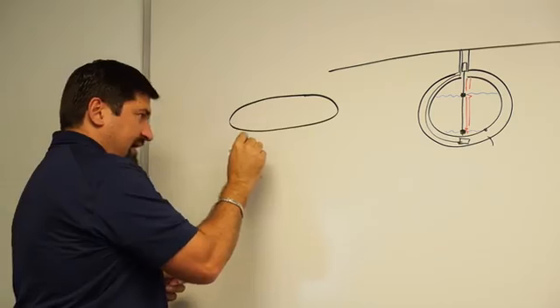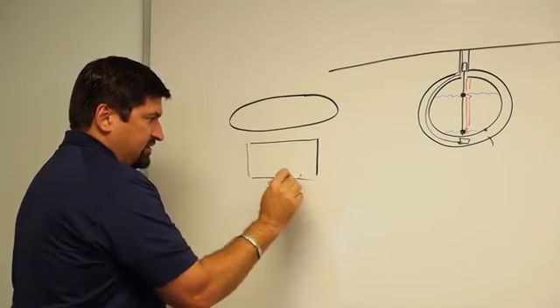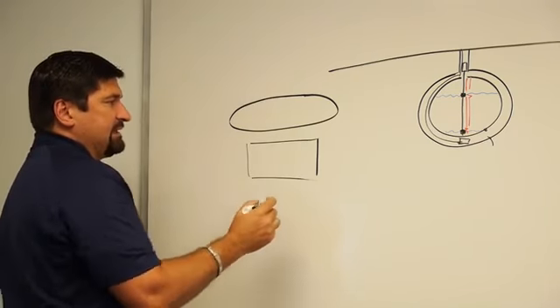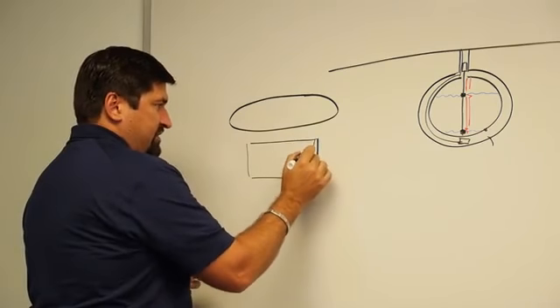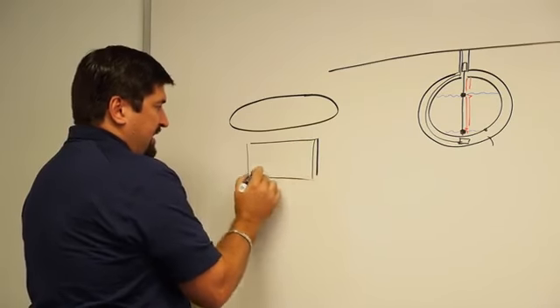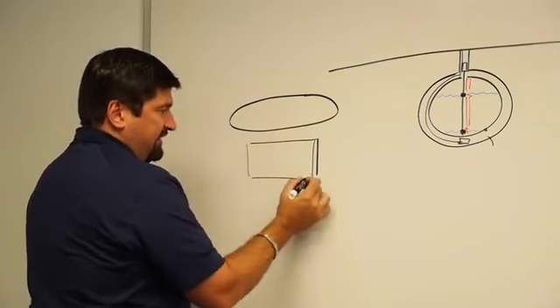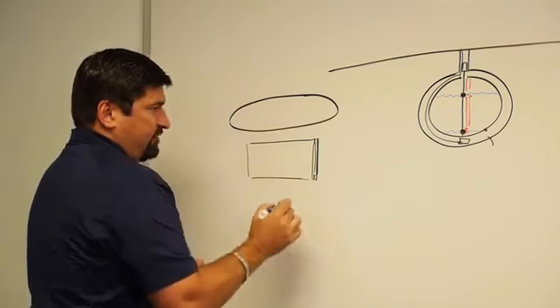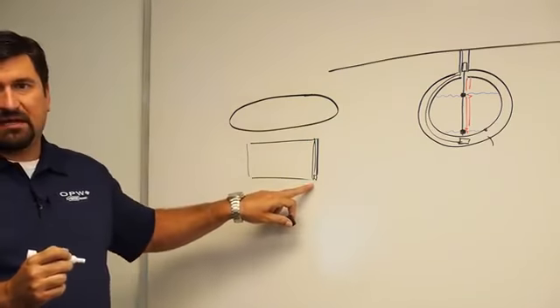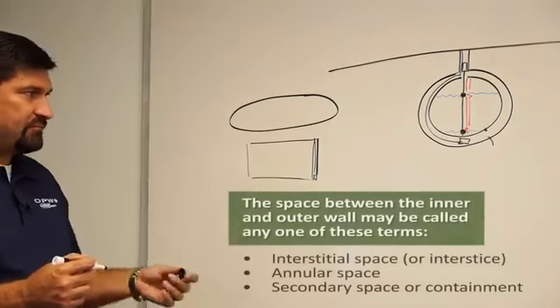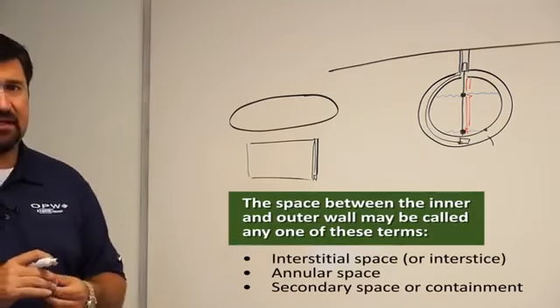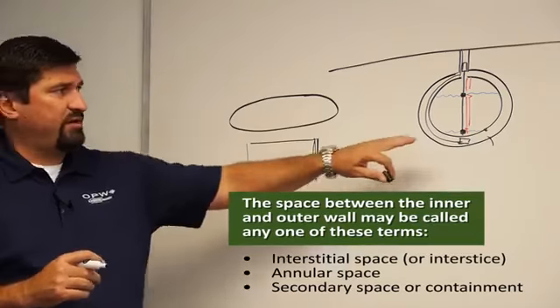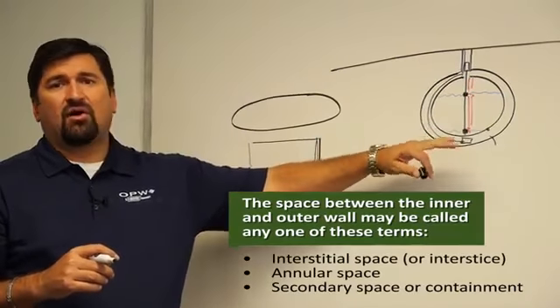Now, they also make a steel tank. It's still cylindrical, but most steel tanks have a flat end, and basically they're just going to run a pipe down to the bottom, and you actually see the secondary of this, but it's strictly just a float type sensor sitting at the bottom of this tank. And they're basically doing the exact same thing. All they're doing is letting you know whether you had a problem in the inner or outer wall of the tank.